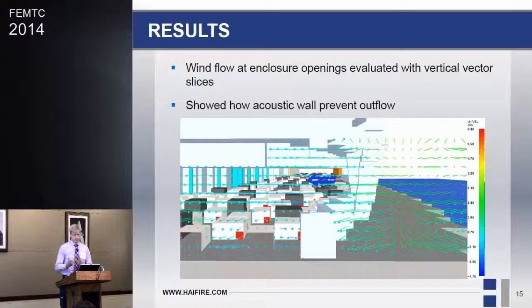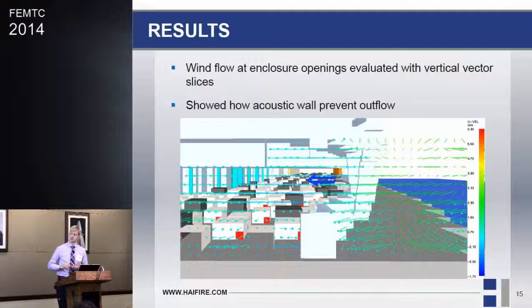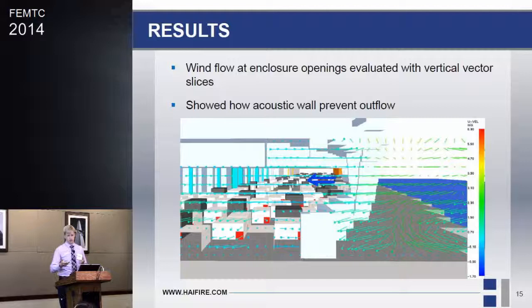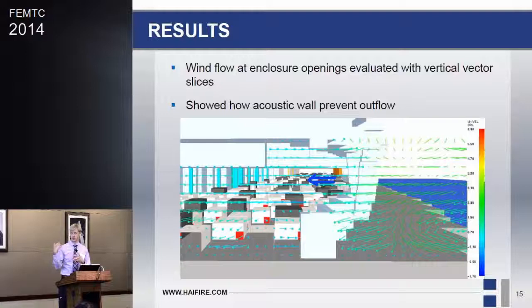There was some back-and-forth about the acoustic wall, so we ran cases both with and without it. Looking at a velocity slice through the roadway, with the wall in place, wind from the river hits the wall and creates a vortex, resulting in only one-directional flow — which leads to CO buildup. Without the wall, we saw lower concentrations because there was bi-directional flow recycling the air back out. But since the wall was going to be built, that's what we used in the final runs.